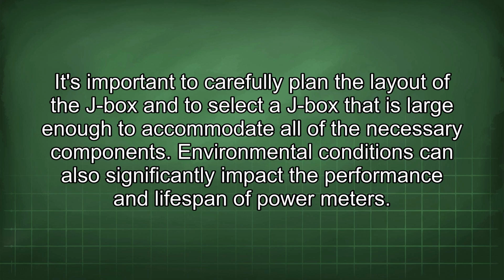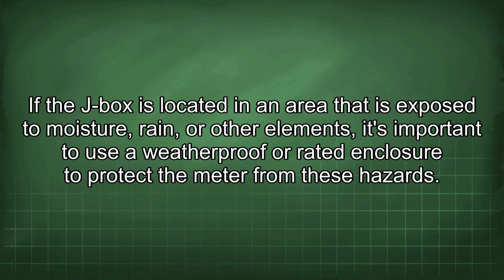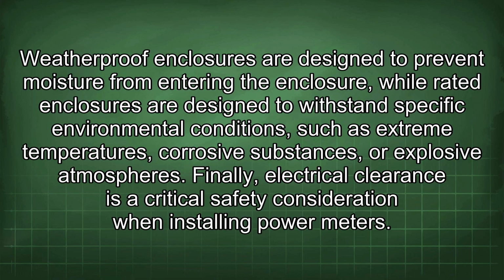Environmental conditions can also significantly impact the performance and lifespan of power meters. If the J-box is located in an area that is exposed to moisture, rain, or other elements, it's important to use a weatherproof or rated enclosure to protect the meter from these hazards. Weatherproof enclosures are designed to prevent moisture from entering the enclosure, while rated enclosures are designed to withstand specific environmental conditions such as extreme temperatures, corrosive substances, or explosive atmospheres.